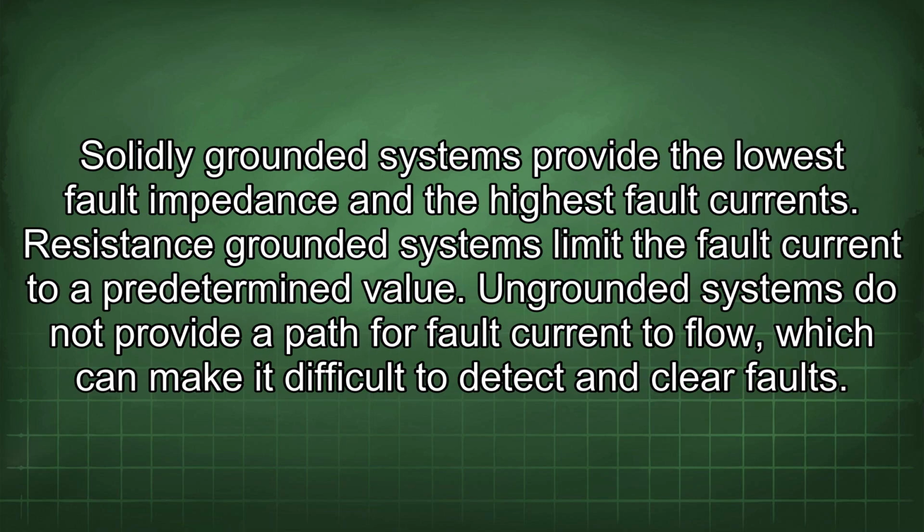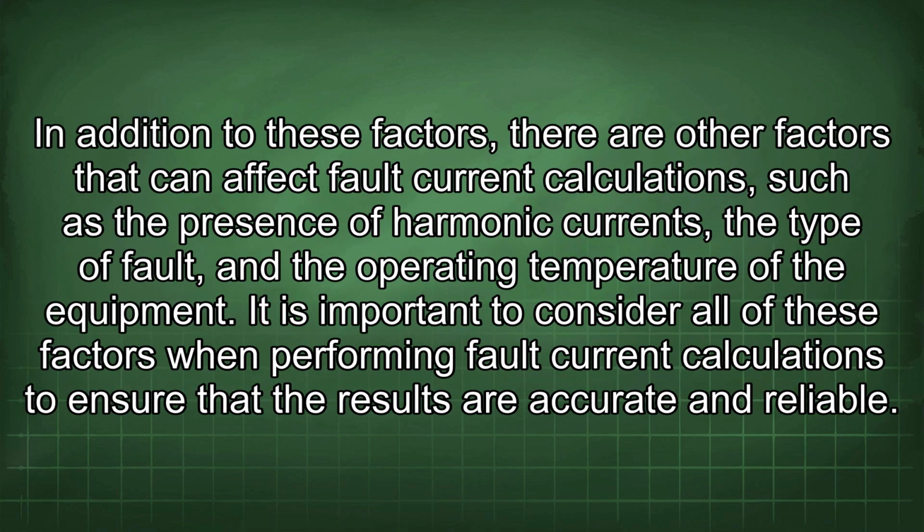Solidly grounded systems provide the lowest fault impedance and the highest fault currents. Resistance grounded systems limit the fault current to a predetermined value. Ungrounded systems do not provide a path for fault current to flow, which can make it difficult to detect and clear faults.